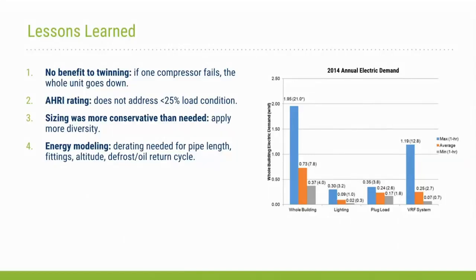One other thing we observed is the AHRI rating process. While it does allow for comparison from one system to another between different manufacturers, it doesn't have a rating condition below 25% as a testing point. This particular building had a lot of conditions of operation where we're under very low demand, where the system doesn't necessarily perform as efficiently. Overall, it performs efficiently, but may not turn down as well as one might anticipate.